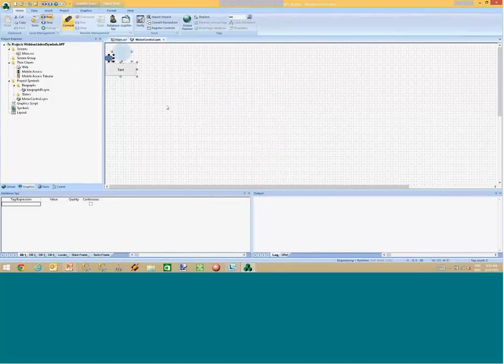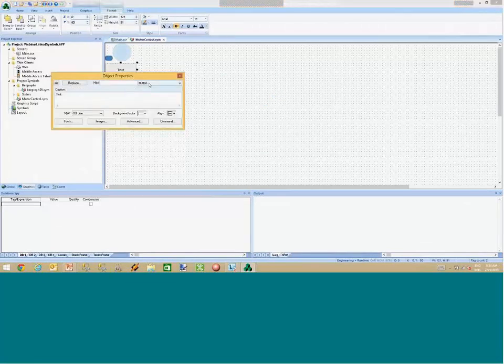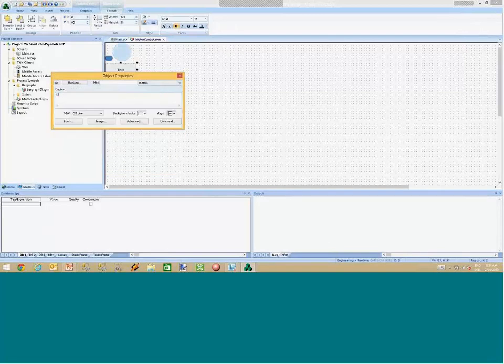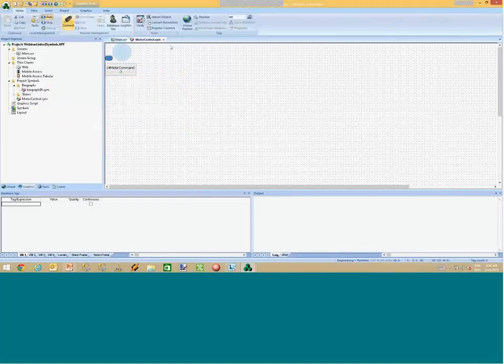And if I want to modify the symbol, I can keep modifying the symbol. So I go to Edit Linked Symbol, and here in the caption of the button, here in the command, I have the property motor command. And here in the caption, I might want to show the value of the motor command. So just define motor command between curly braces, save, and here you have 10101 and motor B independent from motor A. It is a simple symbol, just one custom property, but you can use this concept and create as many symbols as you want.